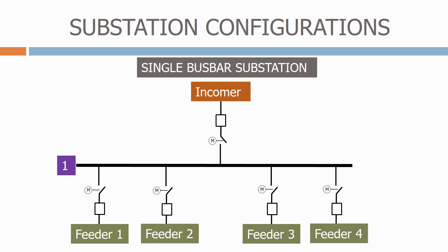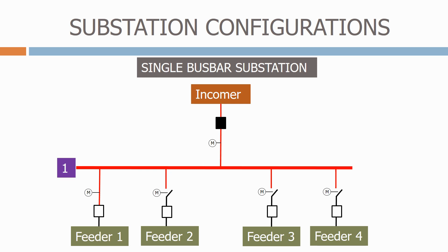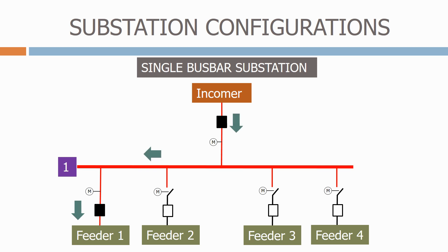Next we have a single bus bar substation. This is a simple configuration to connect a single incomer to several feeders. Firstly we close the isolator on the incomer before closing the incomer circuit breaker. The bus bar is now energised. We then close the isolator and feeder circuit breaker on one of the feeders. Power is now flowing from the high voltage incomer through to the low voltage feeder. The main issue with this configuration is that if the main incomer supply is lost, or a fault occurs on the common bus bars, or it needs to be maintained, all feeders will lose their supplies.